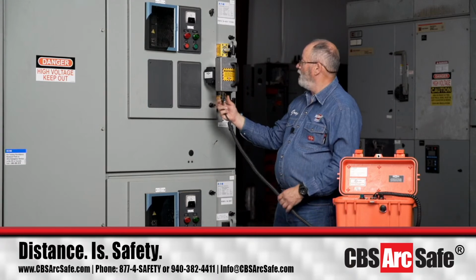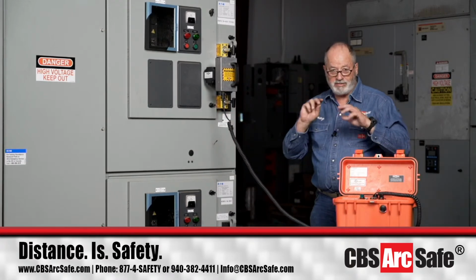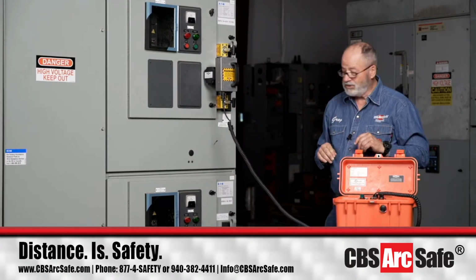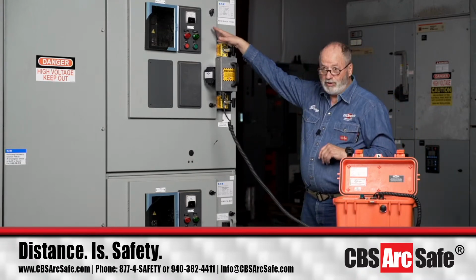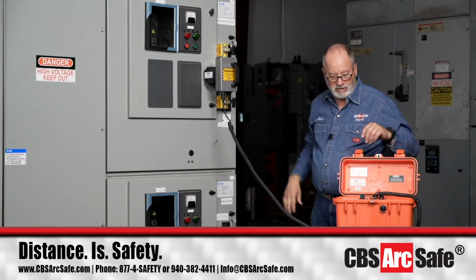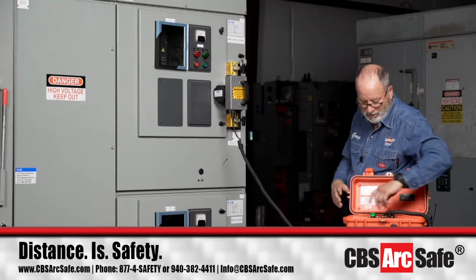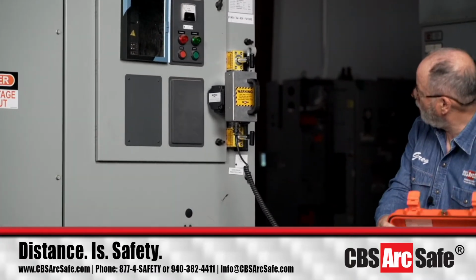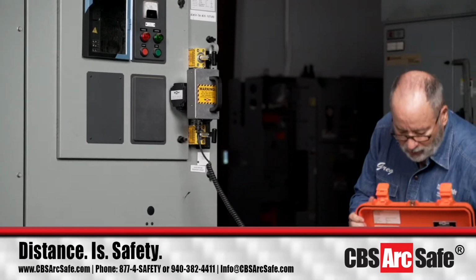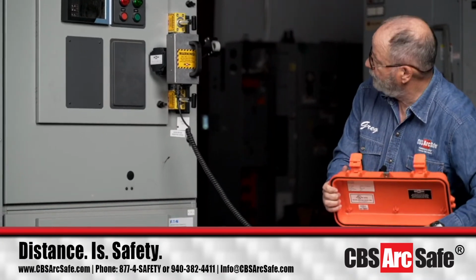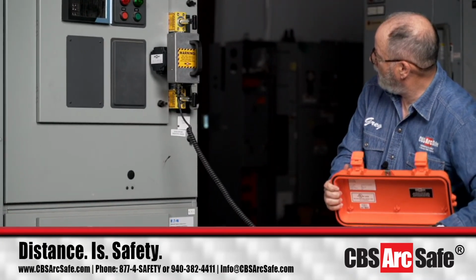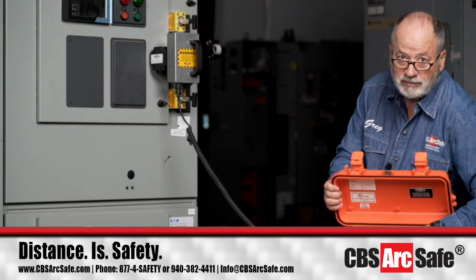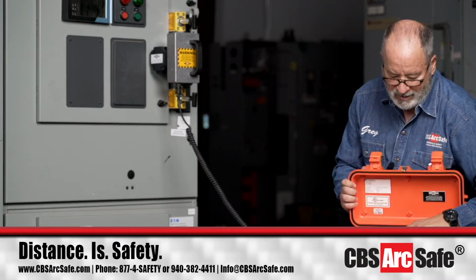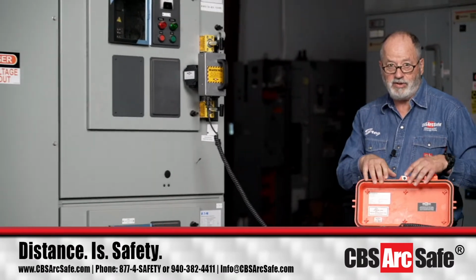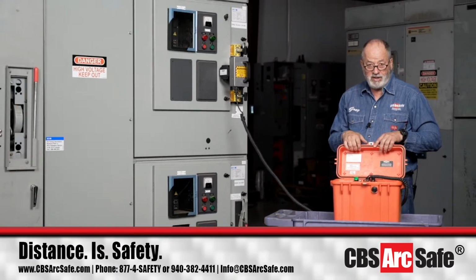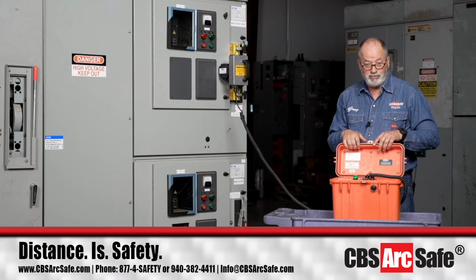This one mounts around the 2 little pre-mount tabs that the Eaton device uses, and you do not have to open the low voltage door for this version. We'll go ahead and turn our power on - we're currently in the closed position, so we're going to trip it, and then close it. And that's the operation of the 2004 and after Eaton Cutler Hammer AmpGard medium voltage motor starter.